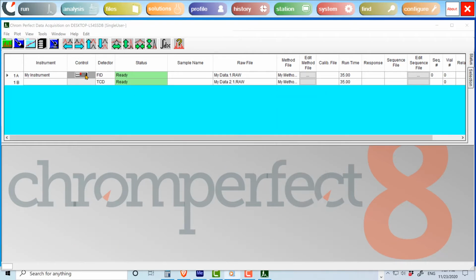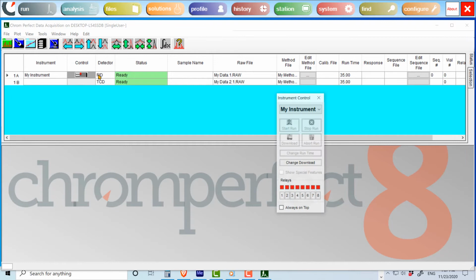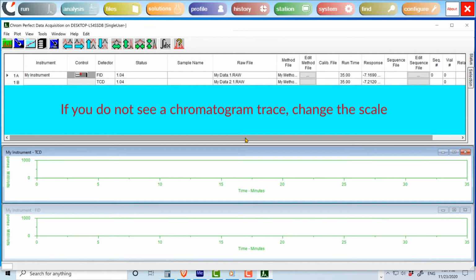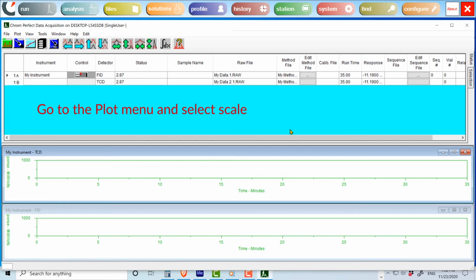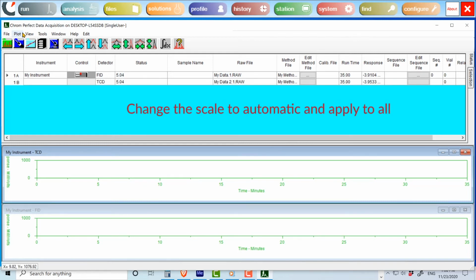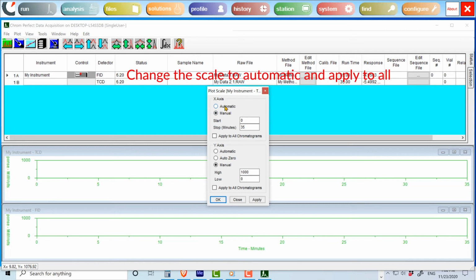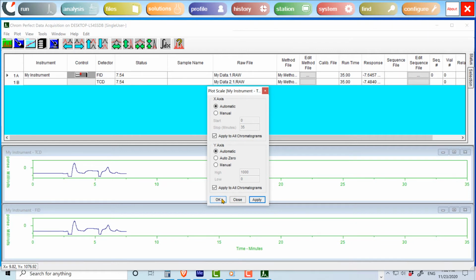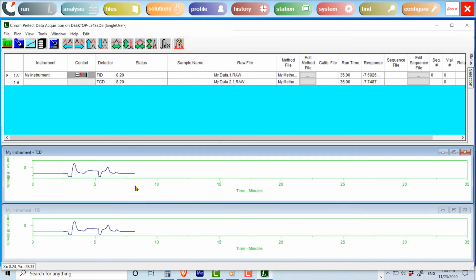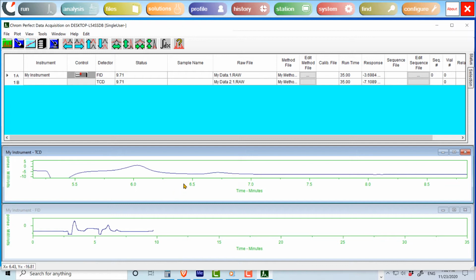Prepare to inject a standard sample. If you have an autosampler, the run should start immediately after the injection. If you are injecting manually, start the instrument as soon as you have injected. In either case, you should see changes in the acquisition program. The instrument status should show the elapsed time and the real-time plot, or plots, should appear. Expand the plot as necessary to see the peaks as they come out.